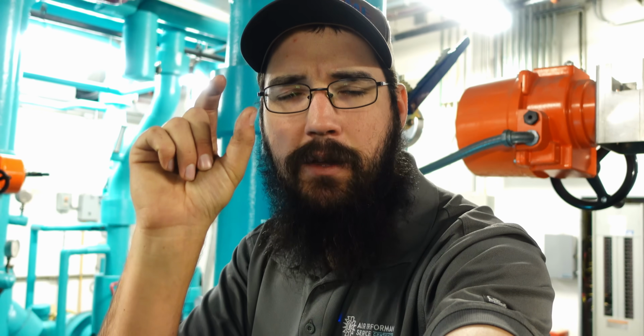And so the point is, when you get down to that very tiny amount of vapor left, as a means of speeding up that last little bit, running those pumps in series should, theoretically, increase that last little bit of pressure pull down versus having them remain in parallel, which is where you get more total volume. That makes a ton of sense as to why it slowed down, because even though I still had a lot of volume to pull, I technically turned my 4-cylinder pump into more of a 2-cylinder staged pump, which is obviously going to move less refrigerant if you have enough volume to feed it.